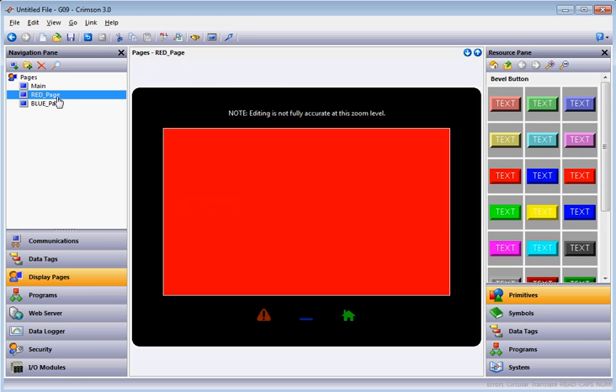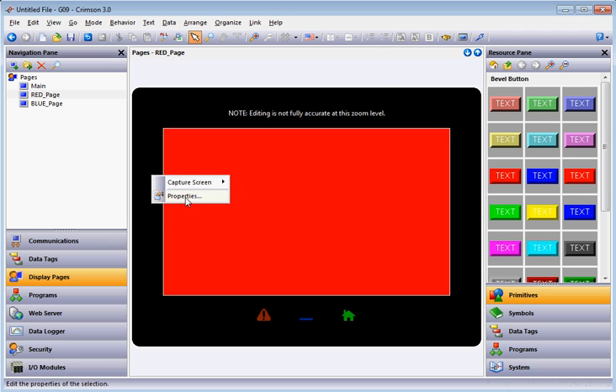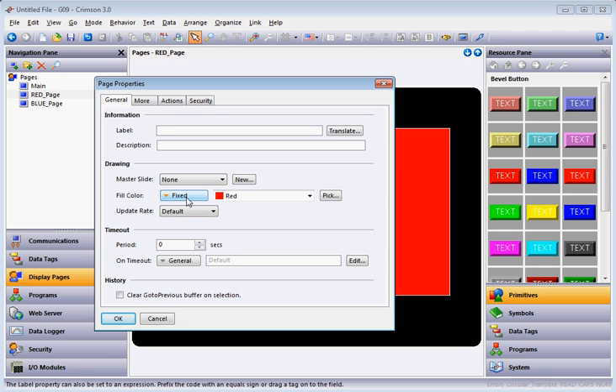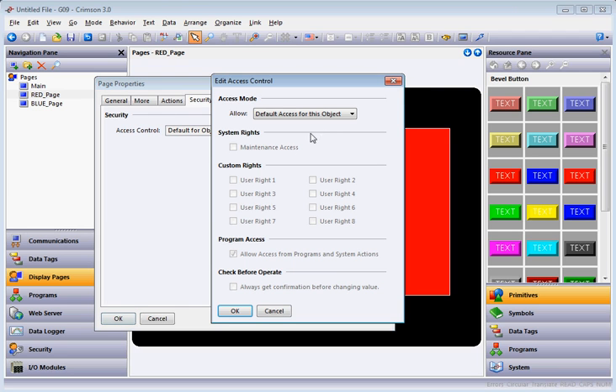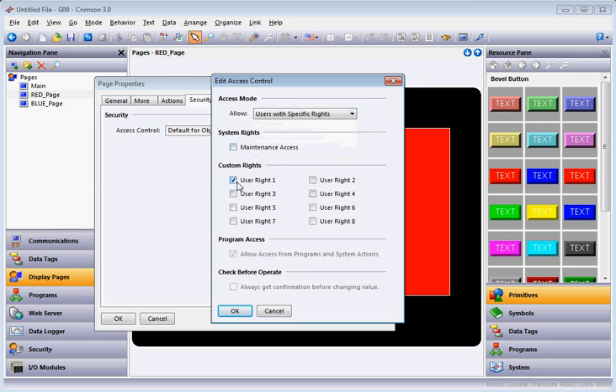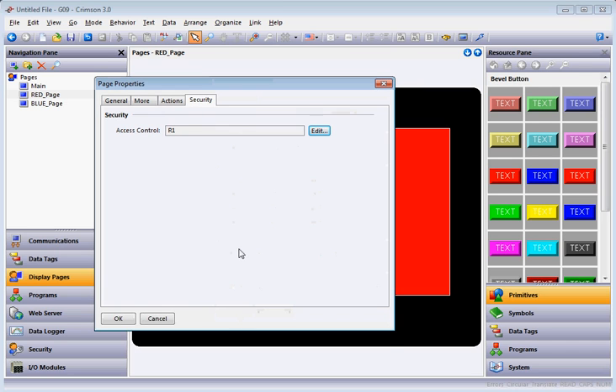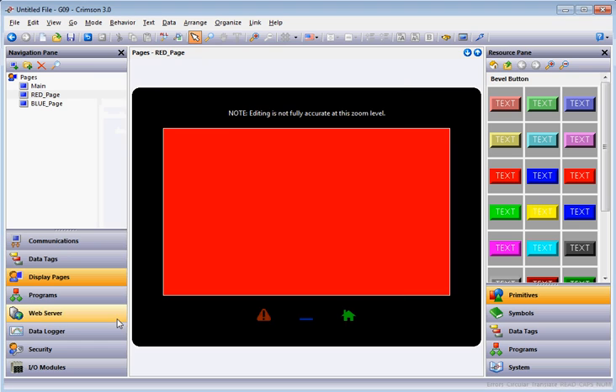Now I'll go back to the display pages and click on the Red Page. The only user who should see this page is the Red User. I'll right click anywhere on the page, go to Properties, and on the Security tab, under Access Control Default for Object, hit the pull-down and choose Users with Specific Rights. I only want users who have Access Rights 1, which is what I set for the red user. Then I'll click OK.